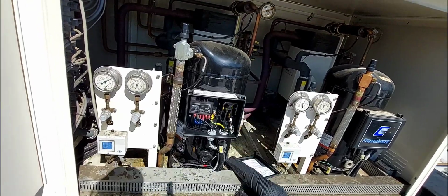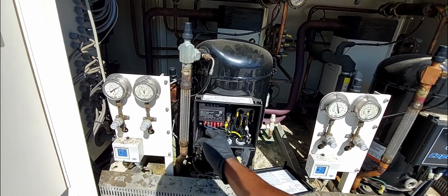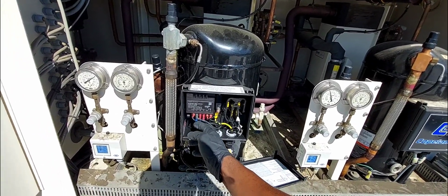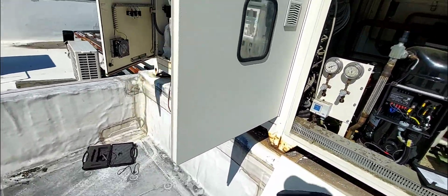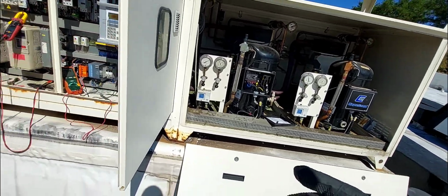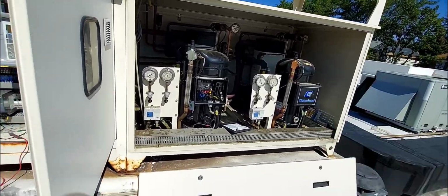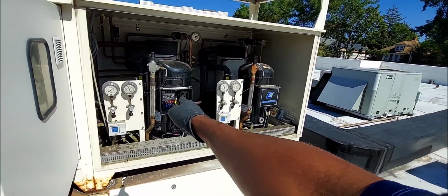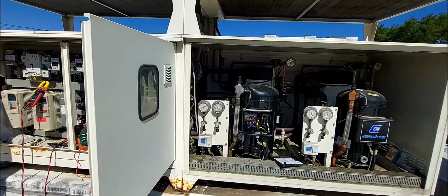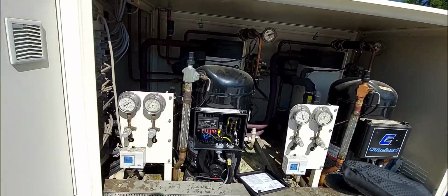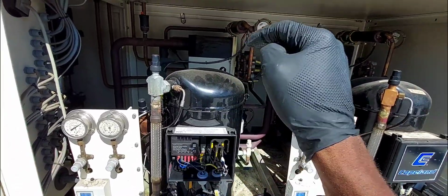Now what that does, I have a video on that. Go and check it out. But in short, what that does is a thermistor here goes internal to the compressor and senses or monitors the temperatures of the winding. One symptom of deteriorated internal compressor windings is that the compressor is going to run hotter, right? It's going to overheat, and that's where that device picks it up and shuts it down. So in this case, given that my compressor is electrically sound, this device here is either faulty or the internal thermistor is faulty.